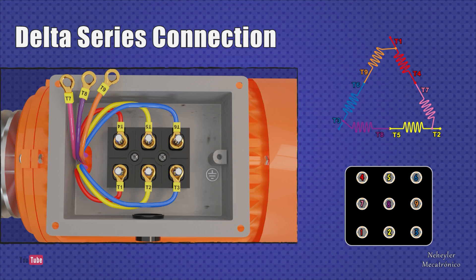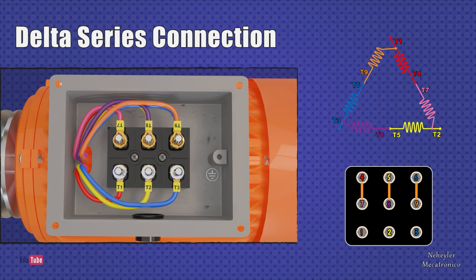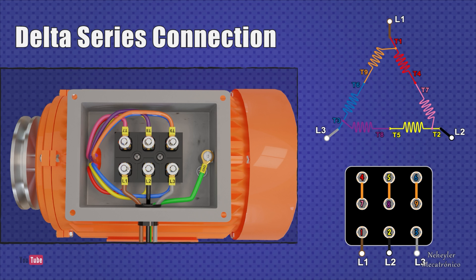In this type of connection, its terminals 1 to 9 are connected in the same way as in the series star type. Terminals T7 must be joined with T4, T8 with T5, and T9 with T6. Finally, it must be fed from Terminal 1 with line 1, Terminal 2 with line 2, and Terminal 3 with line 3.